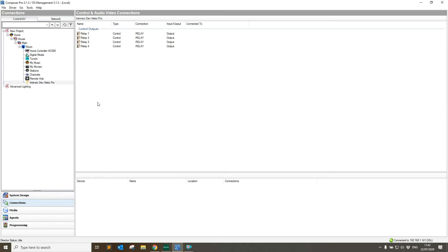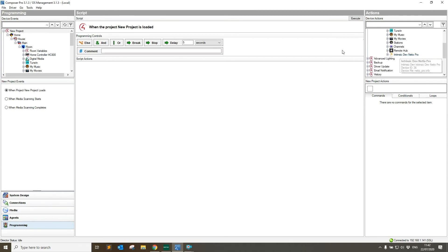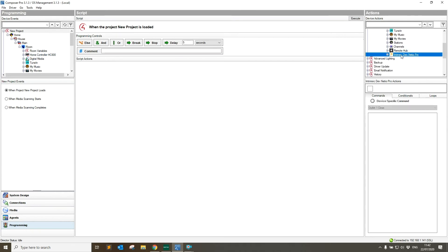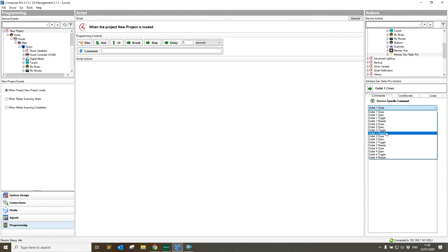If you've got the Netio Pro driver there are some additional options we can do under the programming tab. So if we go to programming and over to the Netio Pro, we'll see there are some device-specific commands. These include a toggle output, which is quite handy, and a restart output. The restart output pauses after power off for several seconds before powering the outlet back on again to ensure a clean power cycle of the device.